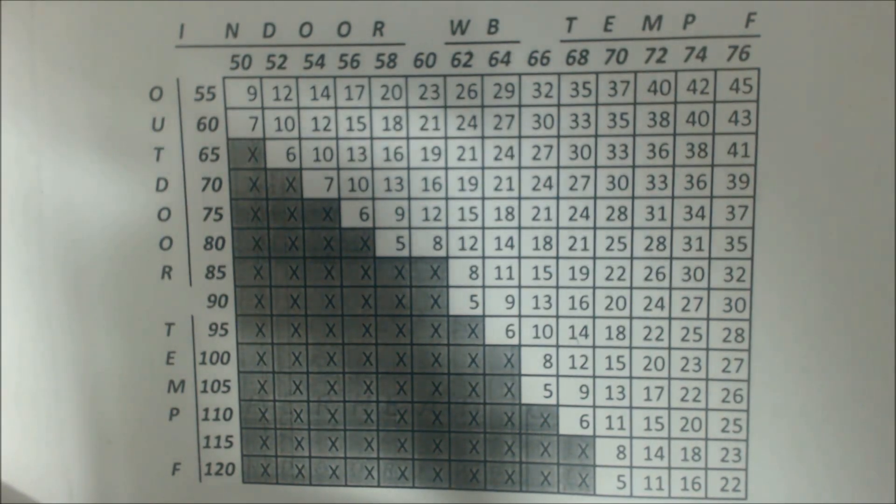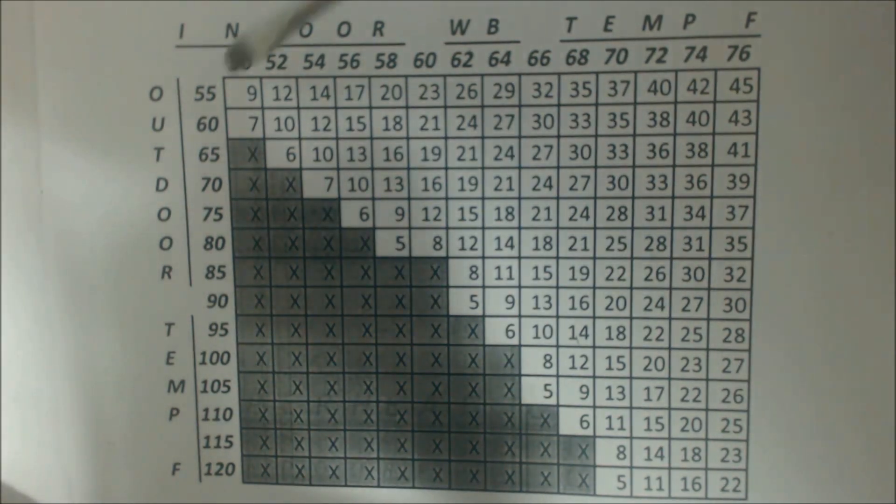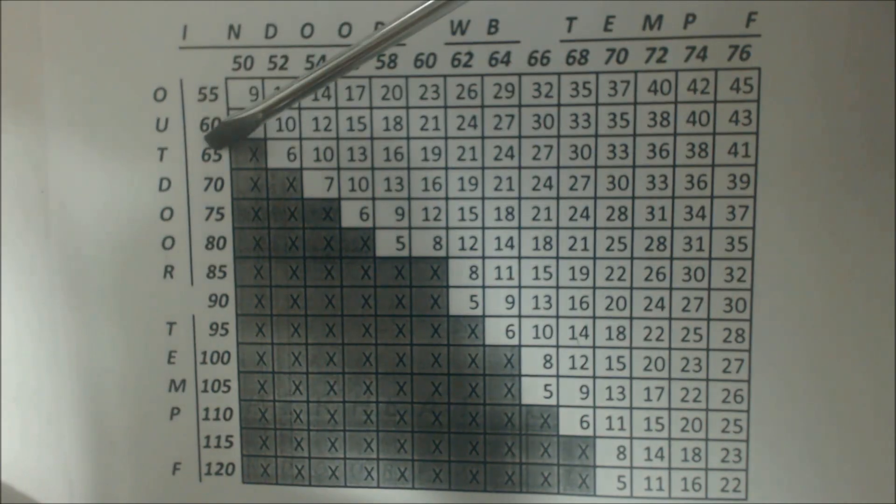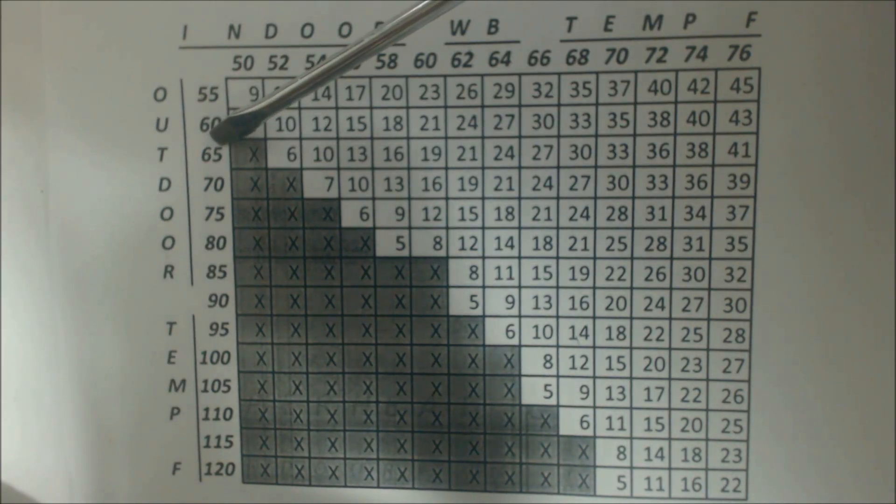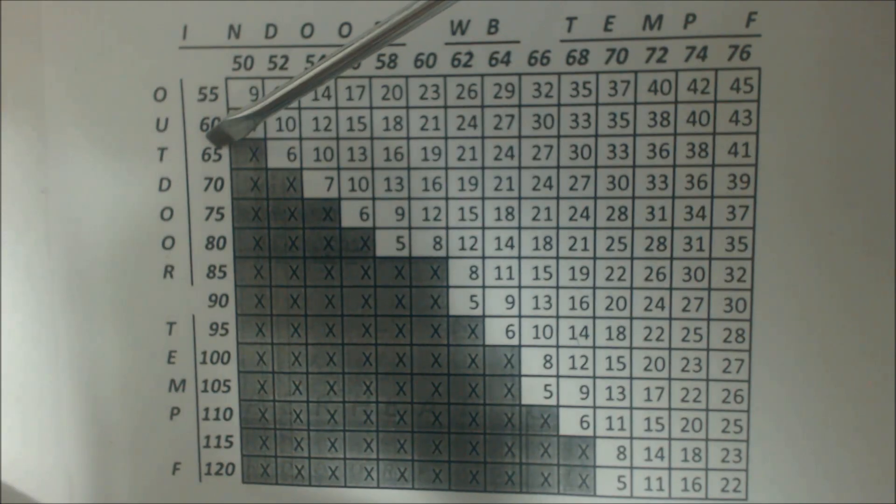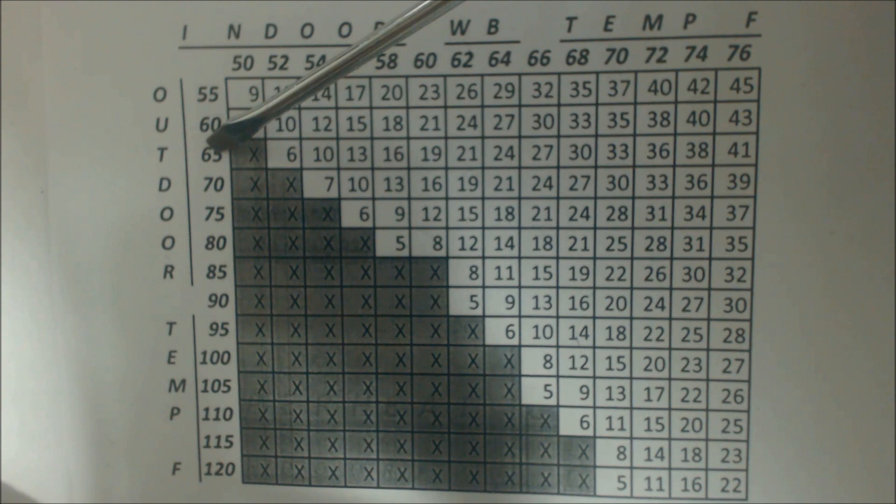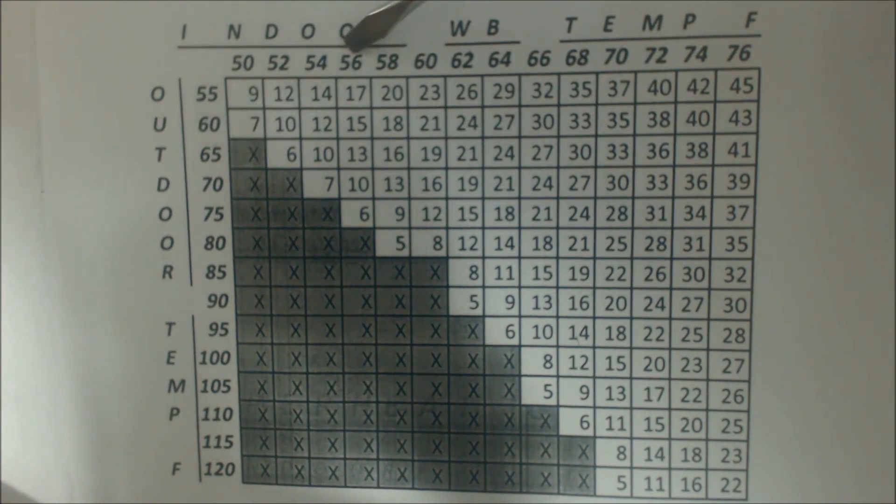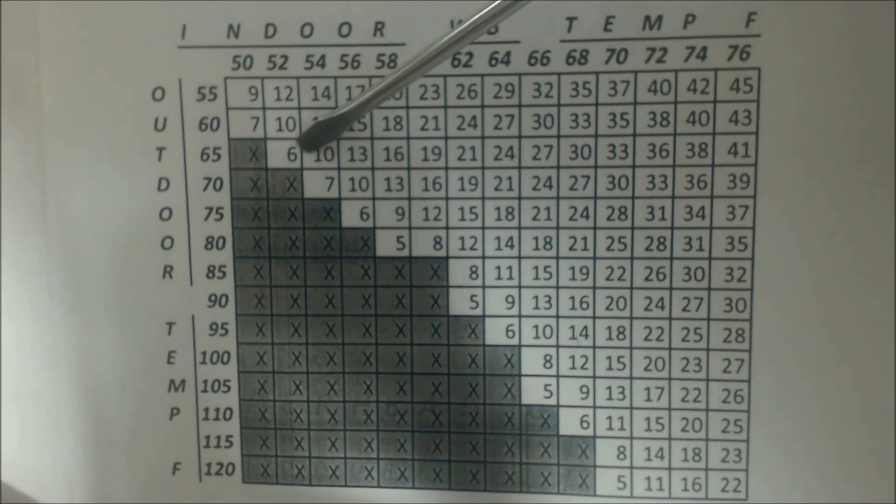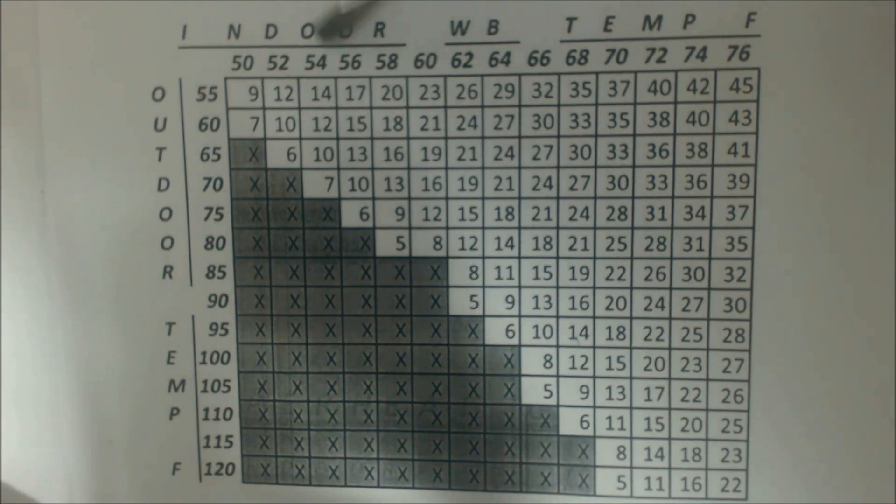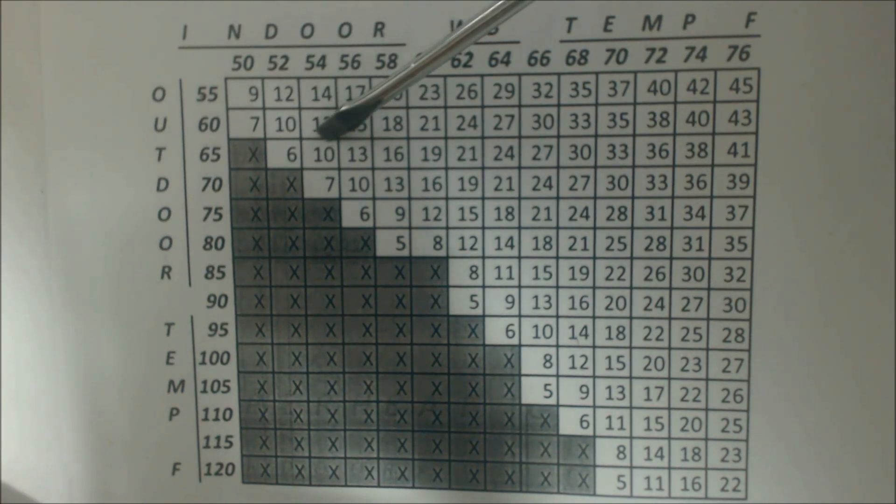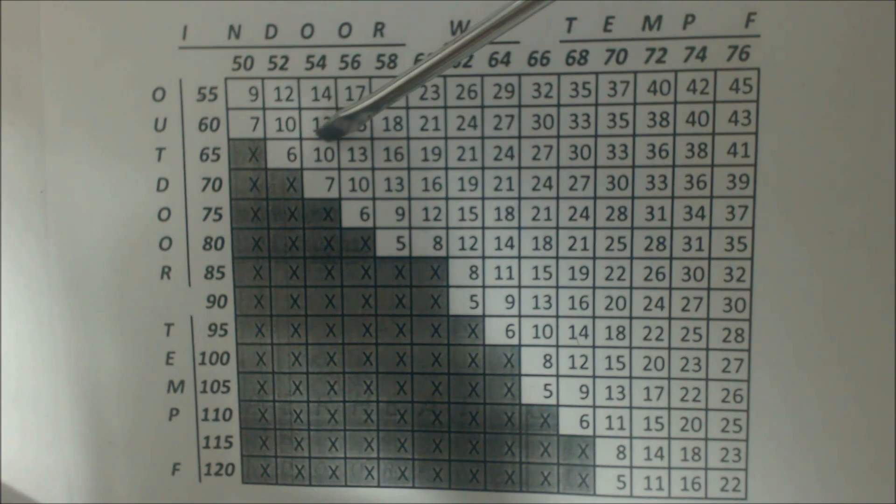Let's just do one more. Say it's 65 degrees, which would be probably the lowest temperature that you would want to check the refrigerant charge in. You want to make sure it has at least 65 degrees outside before you start charging an air conditioning system, just so there's a load on the house. And let's just say it's 54 degrees wet bulb. So 65 over to 54 degrees wet bulb, we find that we're looking for a 10 degree superheat. That's our target.